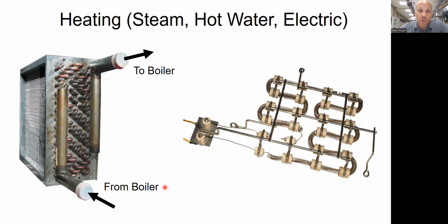So if it's a hot water boiler or a steam boiler, you'll have a coil like this. Once again, air is going to blow through here. I'm going to send it, for example, 180-degree supply boiler water. It's going to fill up this header, and that's going to go up and down the coil. These U-bends on this side have U-bends on the other side that look exactly the same. Come back on row 2 and 3, 4, serpentine back and forth until it comes to this return header. And then my boiler water goes back at 160 to the boiler to be heated up again back to 180, because I've sent 20 degrees worth of heat into that water. So I'm looking for that.